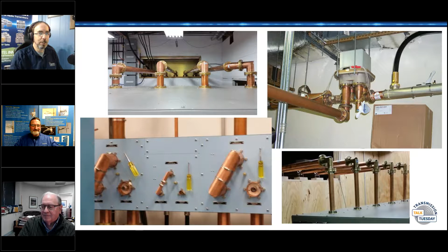Now we were talking thermal imaging, and somebody sent me this one - a perfect example of using a thermal camera to find a potential issue. That was in the region, and the guy was complaining of some intermittent funny sounds, and the transmitter meter was fluctuating. So we took a look at everything inside, went outside with a thermal camera. Red is good, blue and black is good, orange and yellow is bad. We took it apart and got about a gallon worth of soot out of it. You see the inner elbow there, all the carbon and crap all over. That was replaced, and you had to clean out the line in the vicinity of it because the stuff, like a chimney, will travel up the line. Good as new. But again, if you have access to a thermal device, a thermal camera, you can see differences.